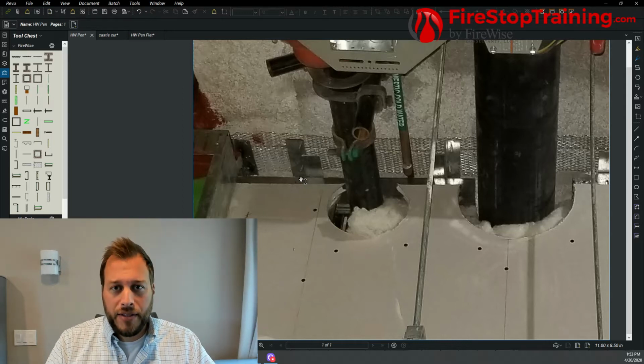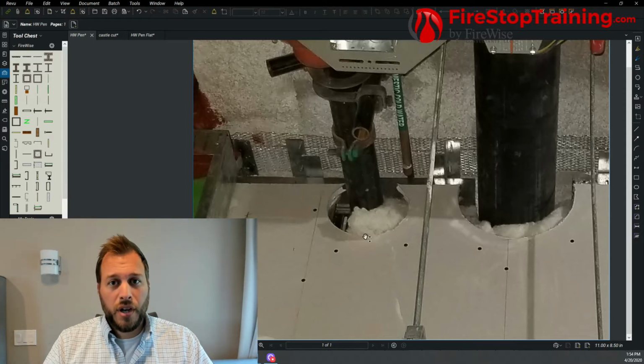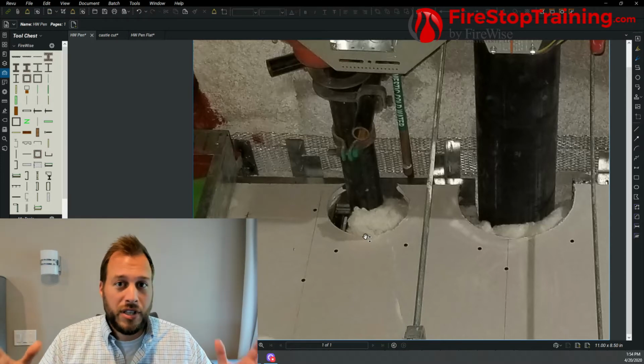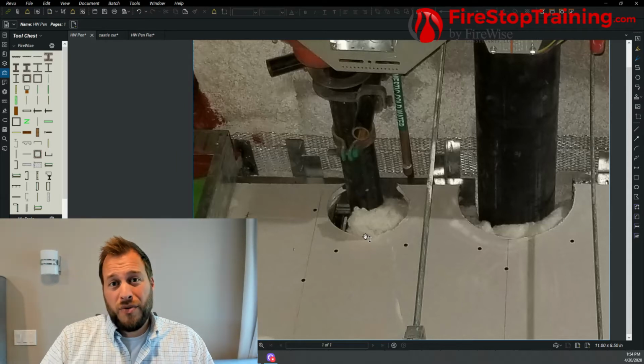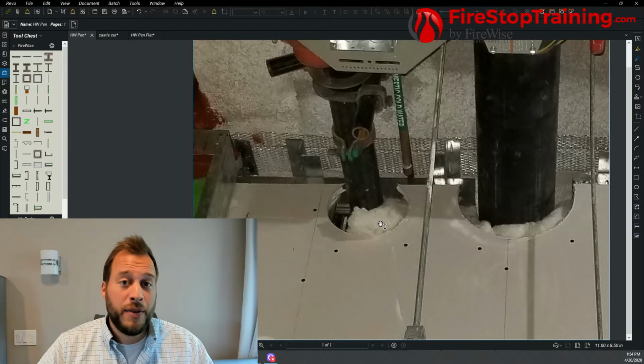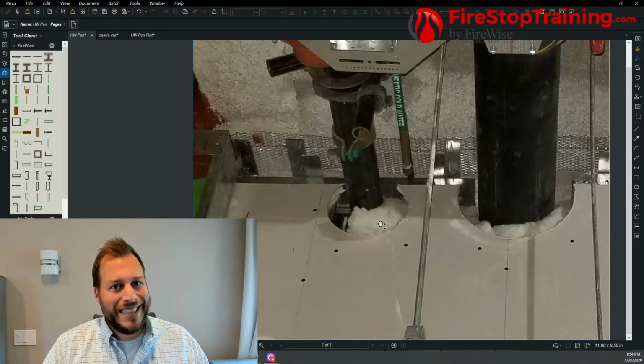So that means when we have a penetration in the joint, it now has to work along with those materials that usually aren't tested for penetrations and have not been tested for movement with this large opening. So to resolve that, many times repair of the wall itself or added framing or different fire stopping materials may be needed, which is not the simple, "Hey Brent, I'm just going to squirt some fire stop around that and spray my head of wall joint. They're all the same manufacturer. It's no problem. Leave me alone." Unfortunately, it's typically not that simple.